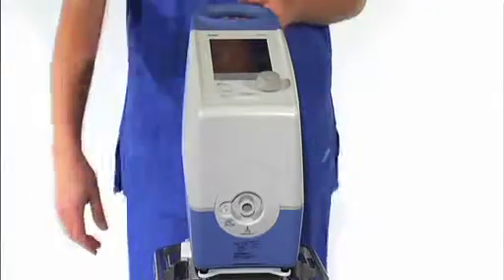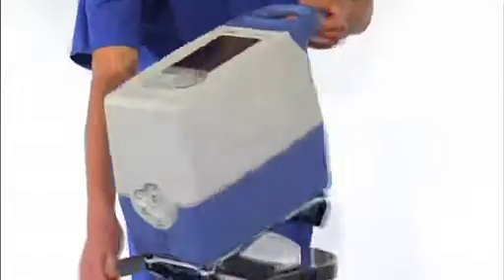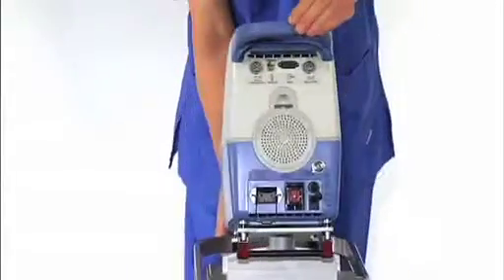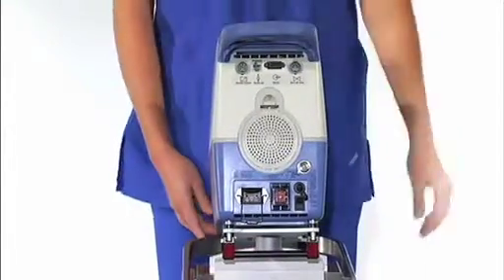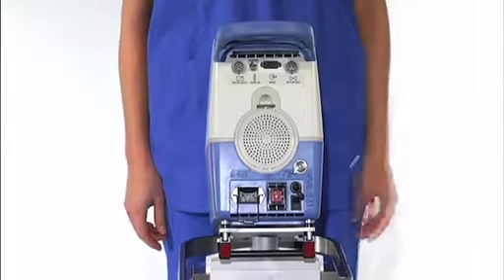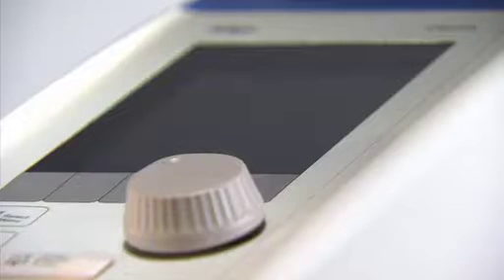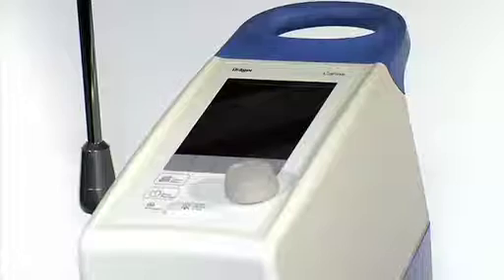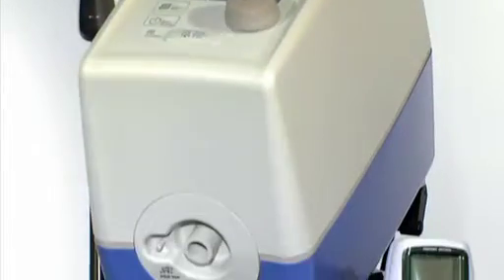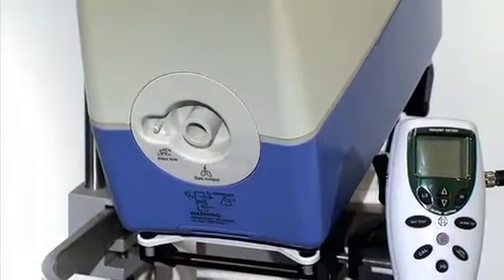Make sure to check that the device is fully functional. This is very important. Any parts showing signs of wear, such as cracks, deformation, discoloration, peeling, etc., should be replaced. Once all maintenance steps have been completed, Carina is ready for the next patient and can be assembled as described in the preparation chapter of the instructions for use.